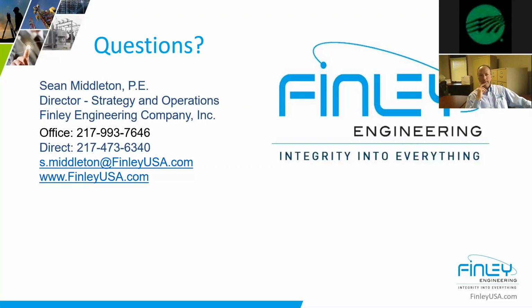Yeah, absolutely. That's what we're doing right now in one case. What we're trying to do is send a trip signal to a distribution feeder in a station to trip off that circuit. And the signal comes from our transmission relay. It happens to work out well there, but the only reason it works out well is because this generator is on a feeder that's protected, that's by itself and has its own breaker. So you're not affecting other customers.